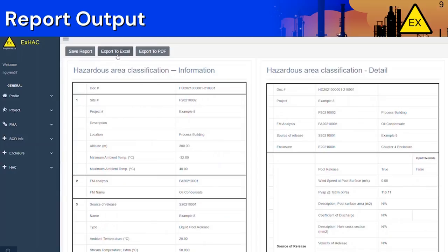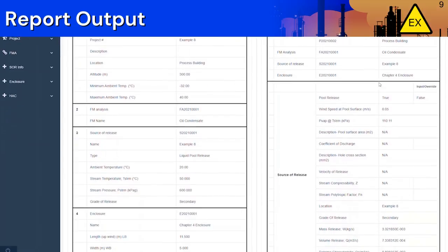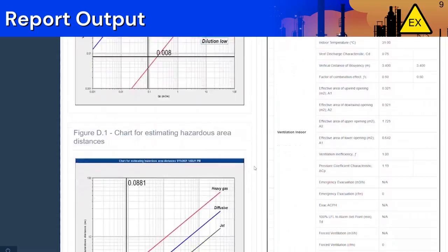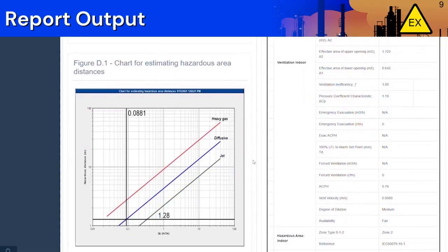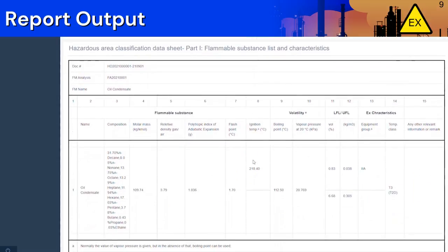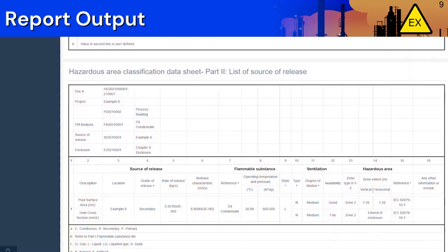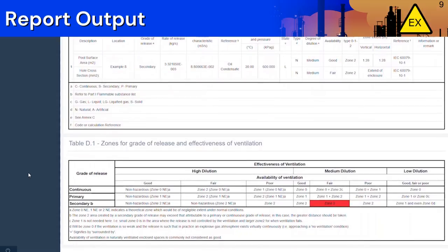The generated report will look like this. The information section displays the input and the detail section displays the simulation results. Figure C1 is created for a graphical representation of the degree of dilution and Figure D1 displays the classification extent. HAC data sheets part 1 and 2 are created based on IEC templates to display the characteristics of the flammable substance and the sources of release.